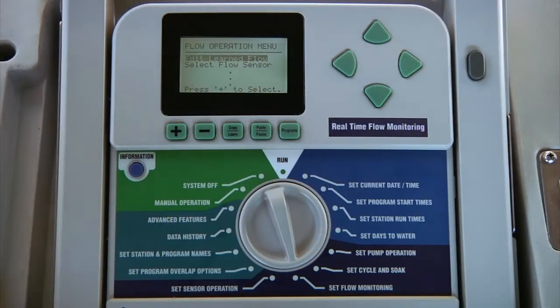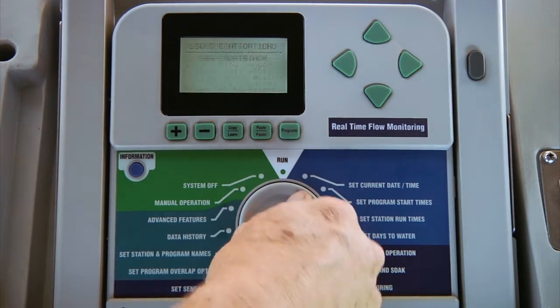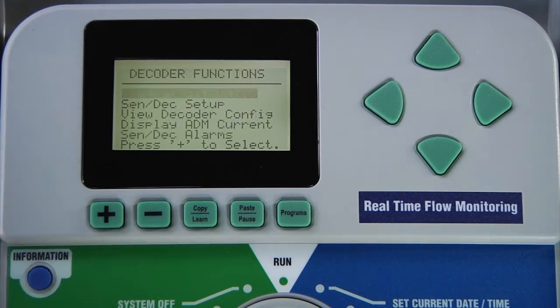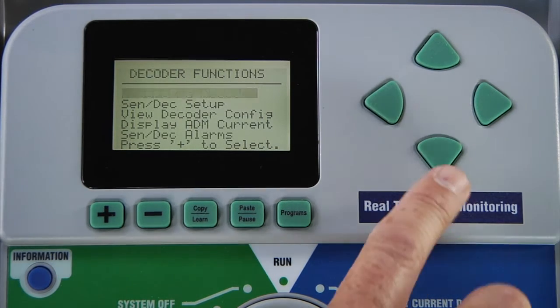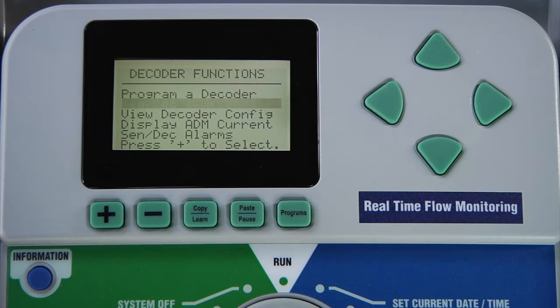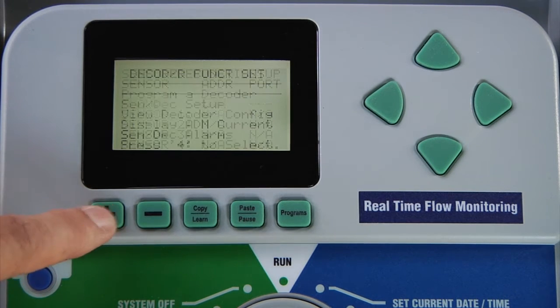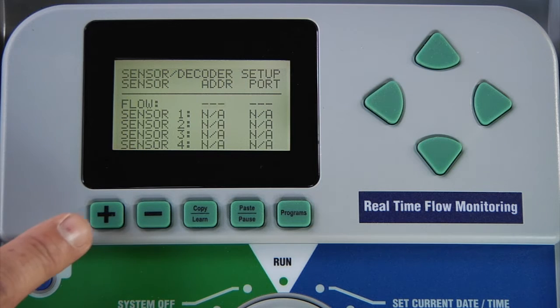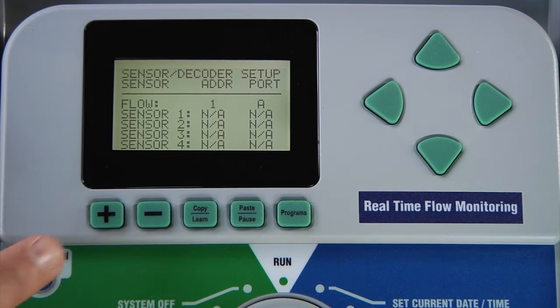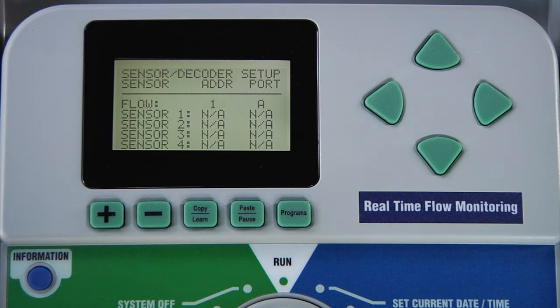To set up a sensor decoder with a flow sensor, turn the dial to advanced features, use the down arrow to go to decoder functions and select plus. From there, the second line says sensor decoder setup. Use the plus to access it. The first line item shows flow. The address you can choose is one through five, and in our case we've chosen address one, so we'll use the plus to go to one. With flow, it will always show port A.